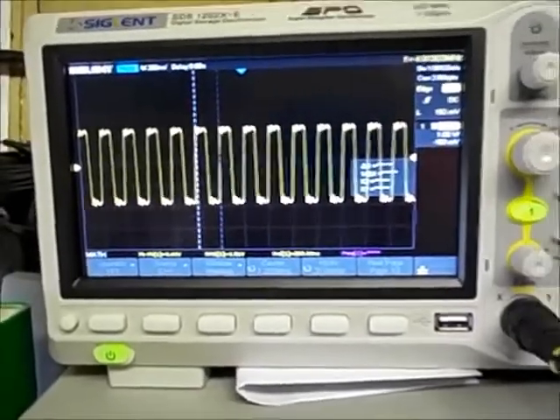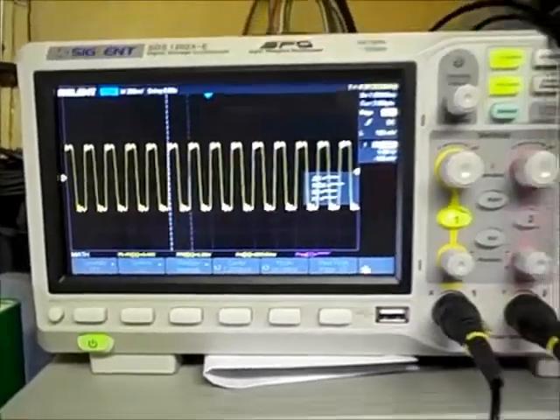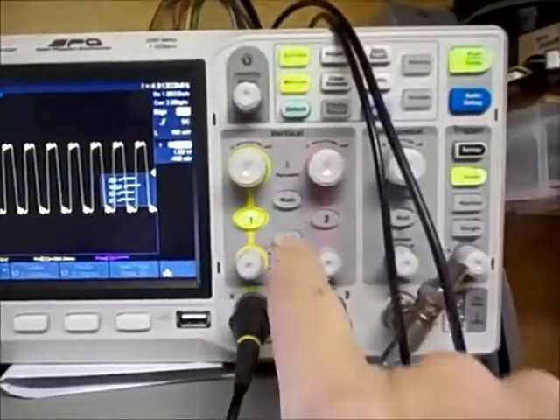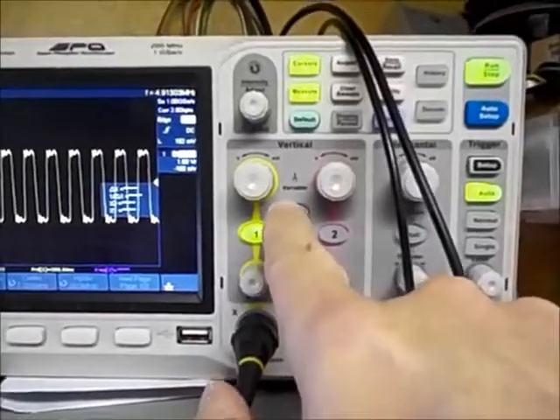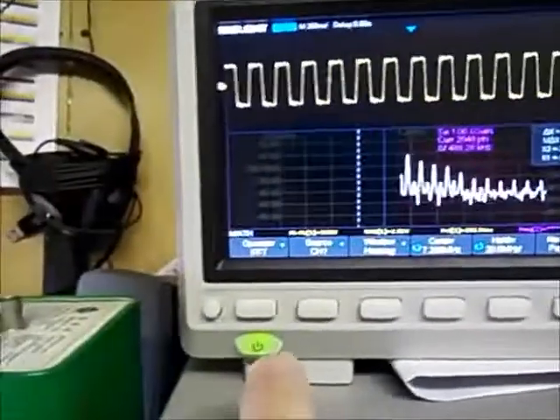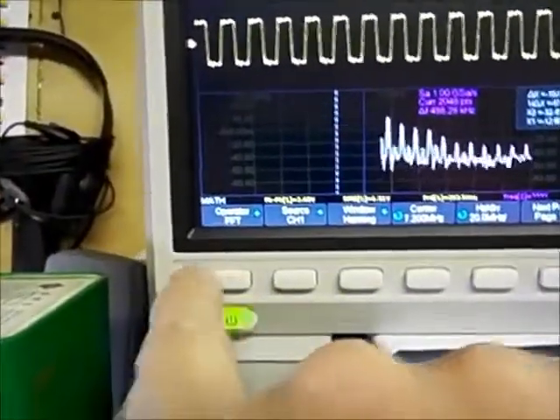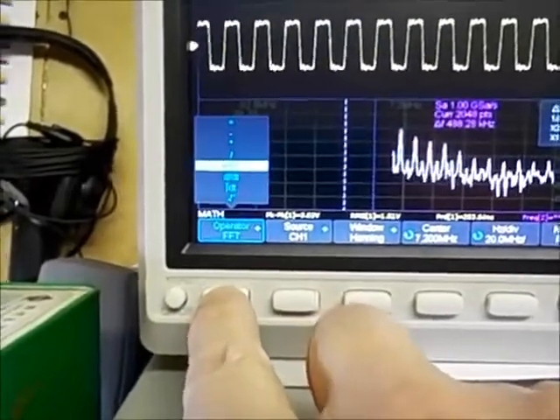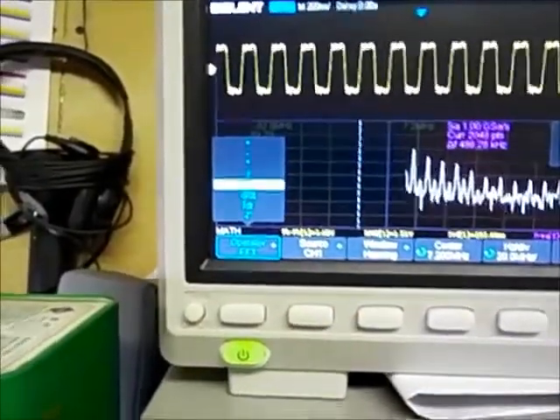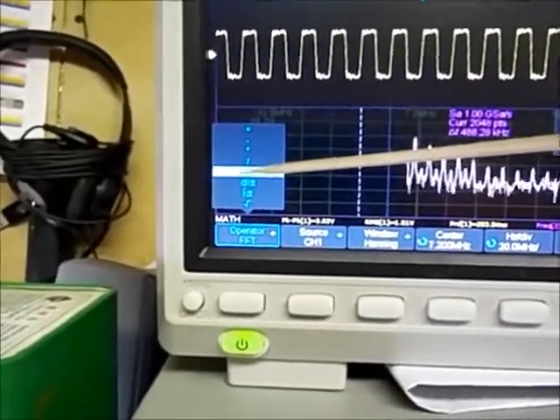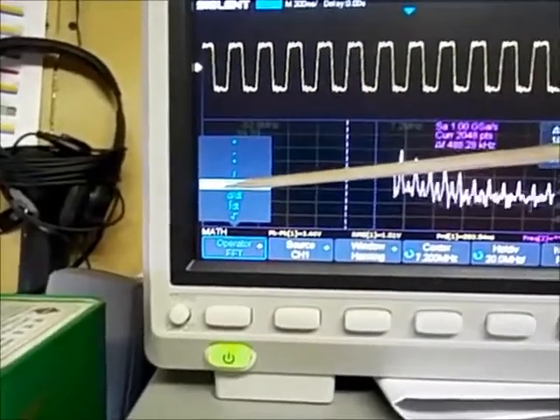The way you would use your FFT is you would hit the math button. Under the math operator, you can select various things, and you would select FFT. Right now it's already selected as an FFT.